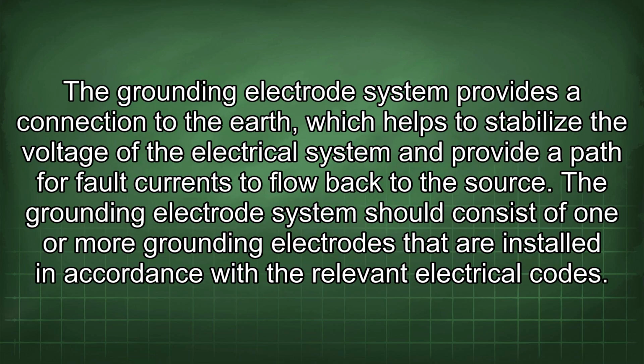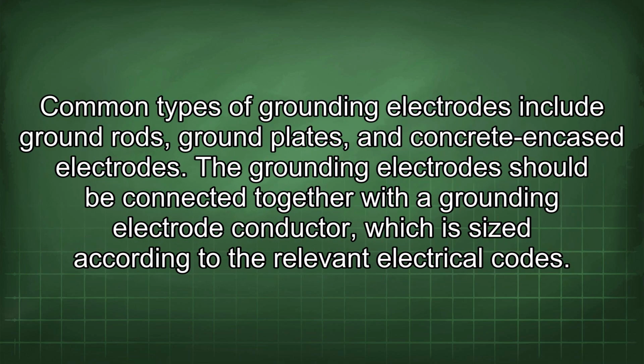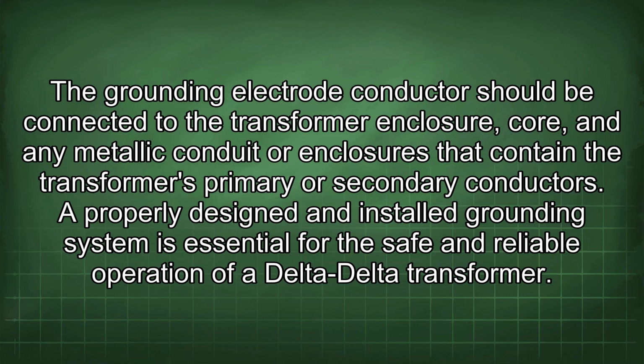Remember that the grounding electrode system is a critical part of the overall grounding system. The grounding electrode system provides a connection to the earth, which helps to stabilize the voltage of the electrical system and provide a path for fault currents to flow back to the source. The grounding electrode system should consist of one or more grounding electrodes that are installed in accordance with the relevant electrical codes. Common types of grounding electrodes include ground rods, ground plates, and concrete encased electrodes. The grounding electrodes should be connected together with a grounding electrode conductor, which is sized according to the relevant electrical codes. The grounding electrode conductor should be connected to the transformer enclosure, core, and any metallic conduit or enclosures that contain the transformer's primary or secondary conductors.